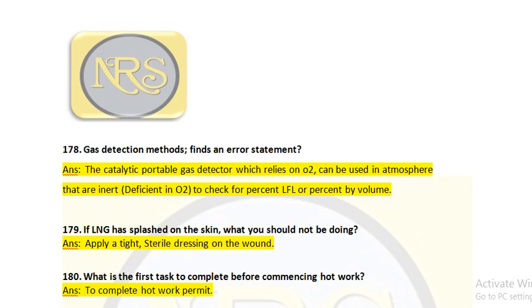Question number 178: Gas detection methods — find the error statement. The catalytic portable gas detector, which relies on oxygen, can be used in an oxygen-deficient inert atmosphere to check the presence of LFL using an explosive meter. This is the error: a catalytic combustion detector works by burning the gas in the presence of air; if there is no air, combustion will not take place. Therefore, you cannot use it in an inert condition since inert gas prevents combustion. This is the incorrect statement.